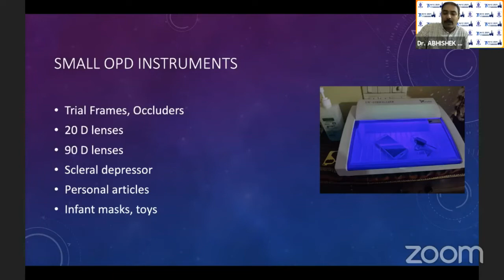Some brands do produce ozone, like I said, and they can cause respiratory symptoms. So if you're using UV light and it's been on for some time, it is better to leave the room open for a short while, 2-3 minutes is sufficient. Continuous UV exposure can cause discoloration of plastic. You see the top photo, that is covered by Zeiss. One is my fundus camera, the other is the OCT in my room, which is not exposed to the UV light. You see the amount of discoloration that has happened. So your plastics will look aged if you expose them to UV light quite a bit.